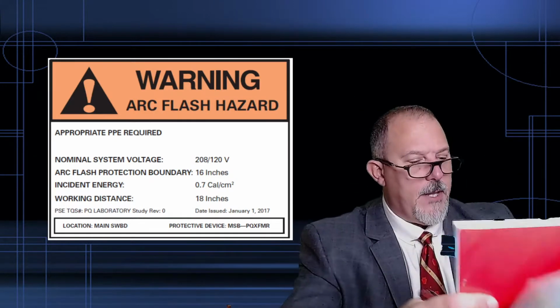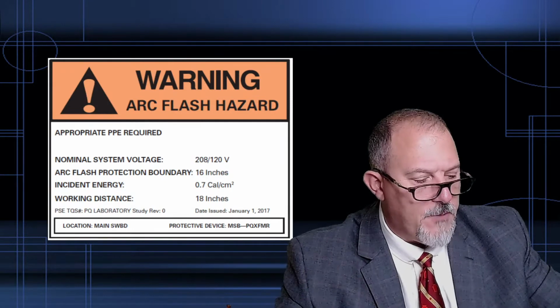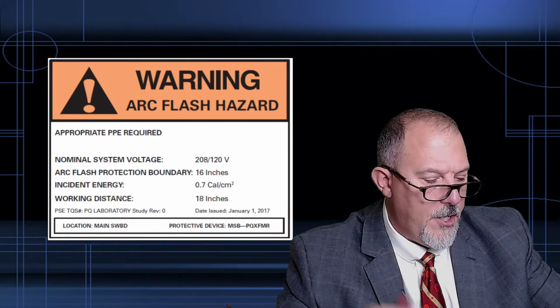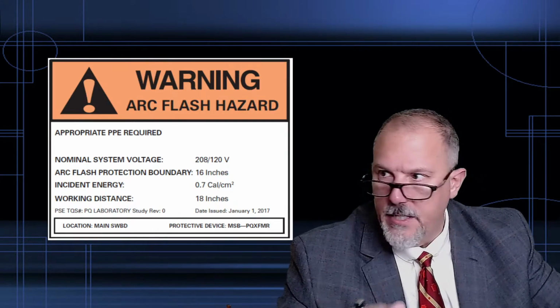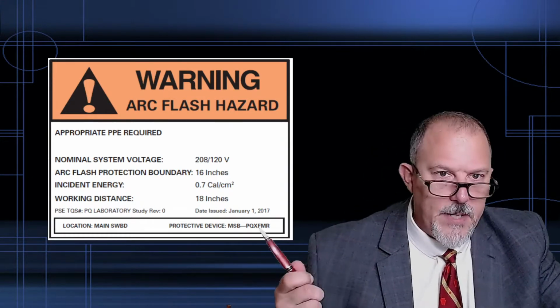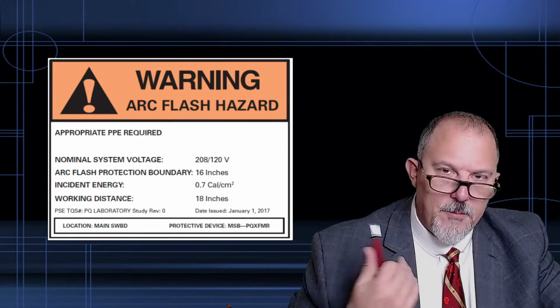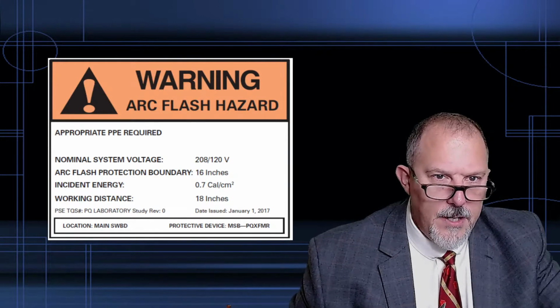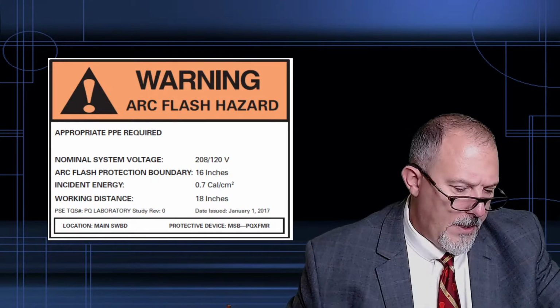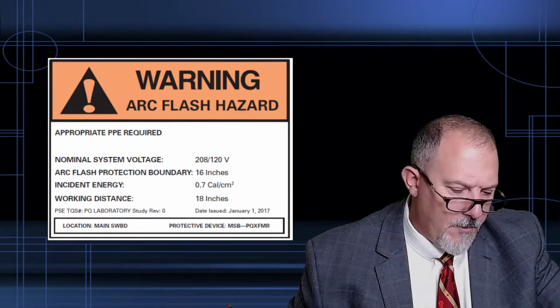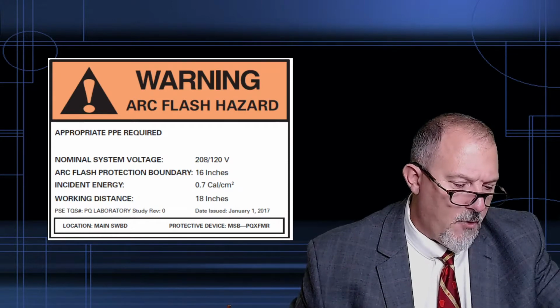So 70E tells us for equipment labeling, I need to have the nominal system voltage, arc flash boundary, at least one of the following. You have to have the incident energy and corresponding working distance. There's my working distance. There's my incident energy. And that helps me understand how to dress. And then it says, and then minimum arc rating of clothing or site-specific level PPE.